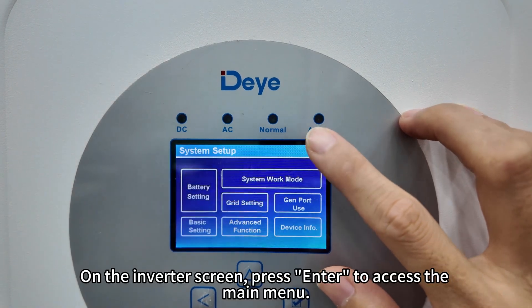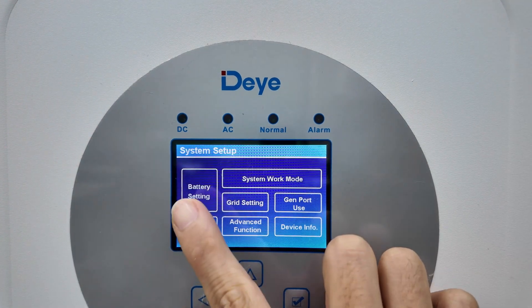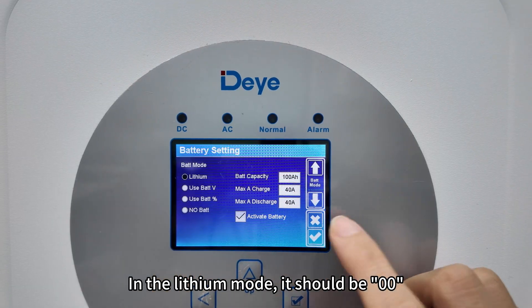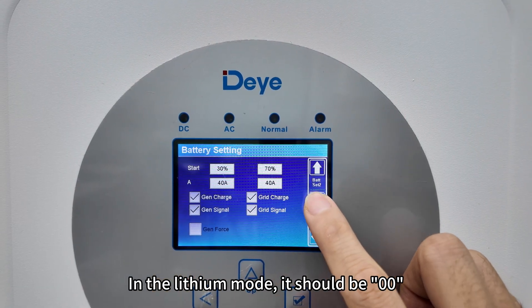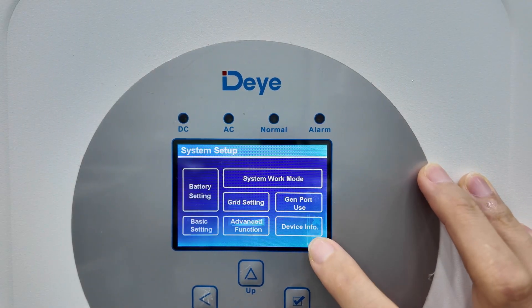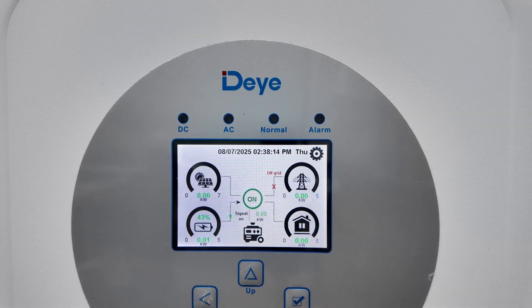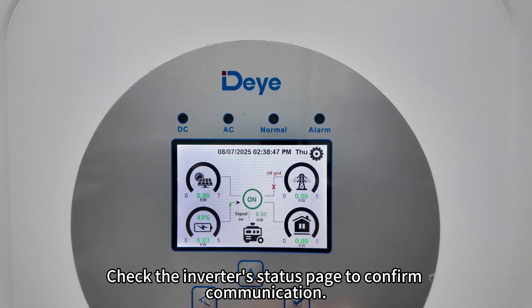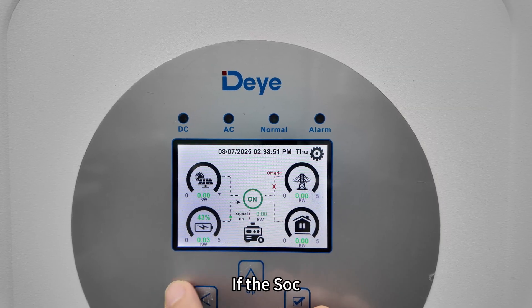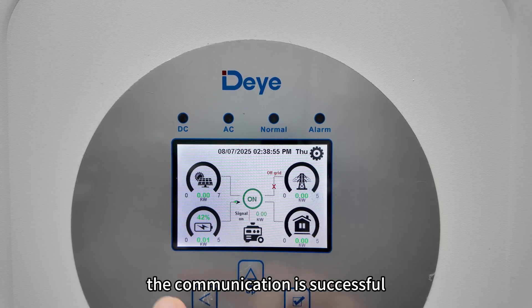On the inverter screen, press Enter to access the main menu. In the lithium mode, it should be double zero. Check the inverter's status page to confirm communication. If the SOC, voltage, and current from the battery are displayed, the communication is successful.